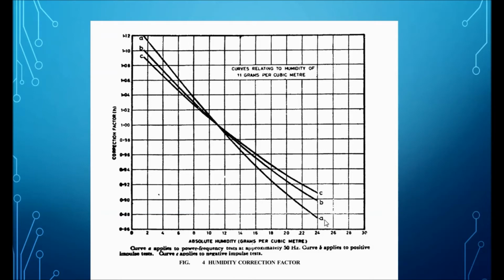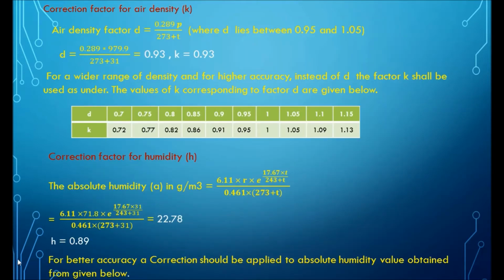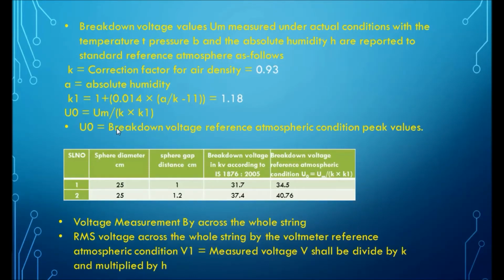A represents the AC power frequency. You can see it is already mentioned here. Then H is 0.89. Now calculate the sphere gap voltage in atmospheric condition. You can see the sphere gap diameter is 25 cm. First set it to 1 cm. At that time the flashover voltage is 31.7 according to the IS standard.